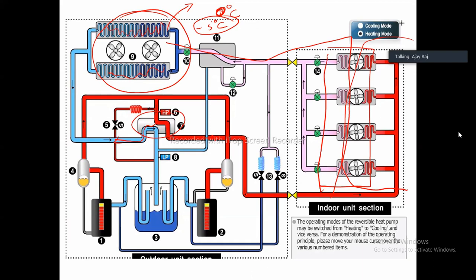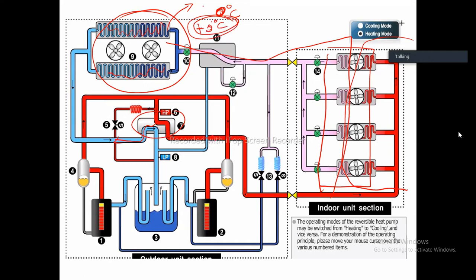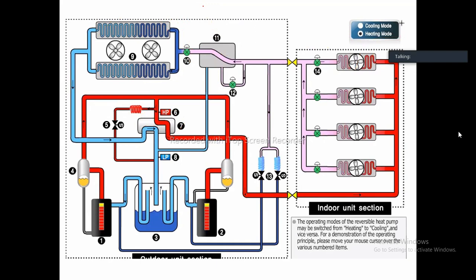If I am using external heaters, this cooling coil, which can reject heat only if it's at -5, will become positive in temperature. If this becomes positive, that means I will not be able to reject heat outside.